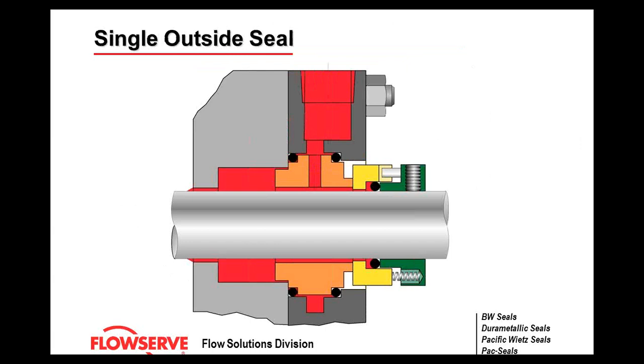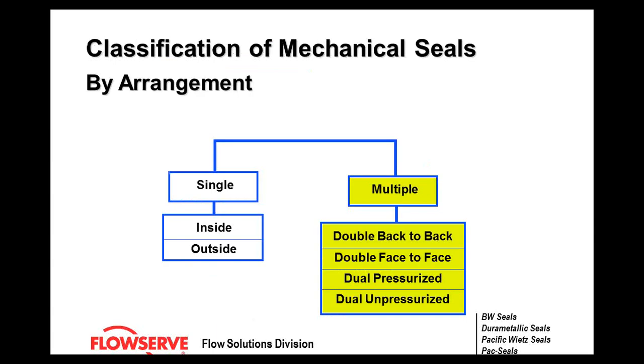Here's an outside seal design — the rotating part and seal faces run outside of the process. You use this design if the stuffing box clearance isn't big enough for a mechanical seal inside, or if you have lots of dirt and grit that could plug the springs, causing a failure, or if you have highly corrosive material and you want to keep metal parts out of that corrosive environment.